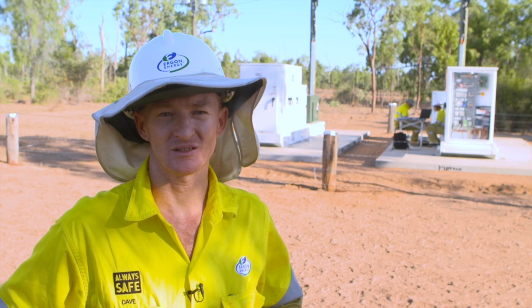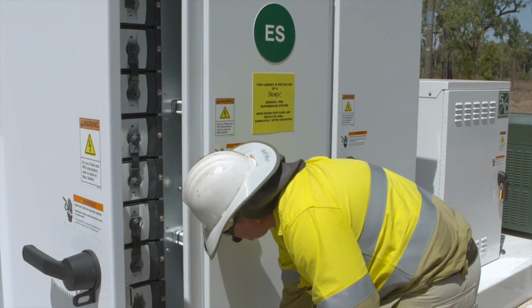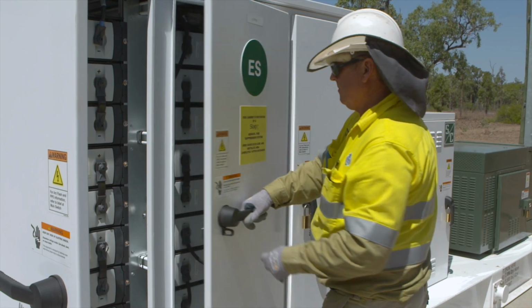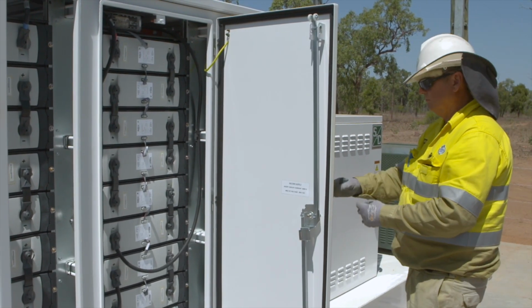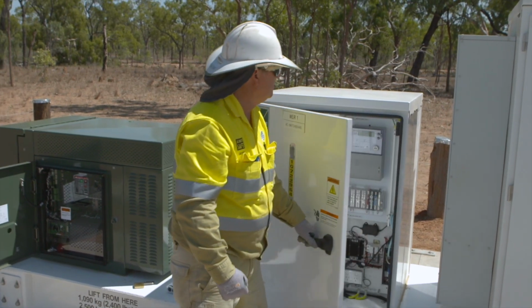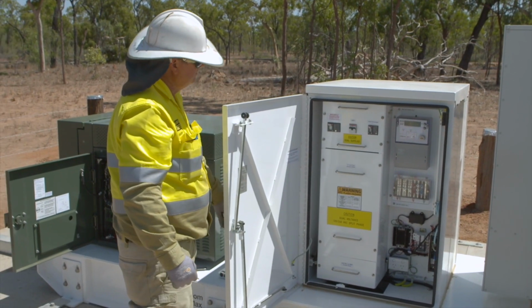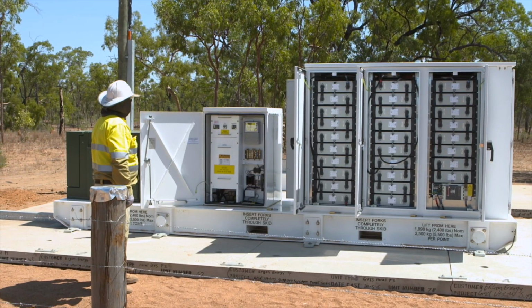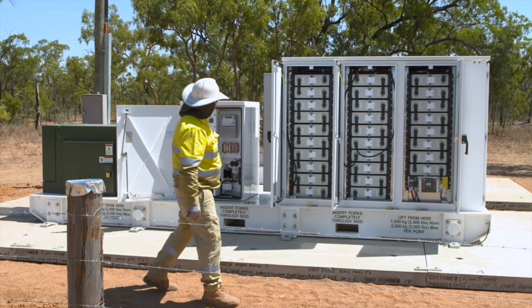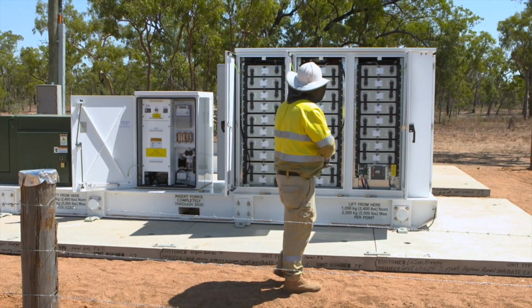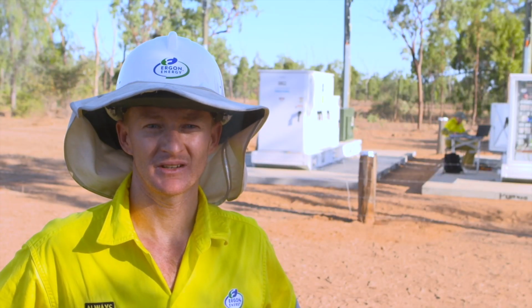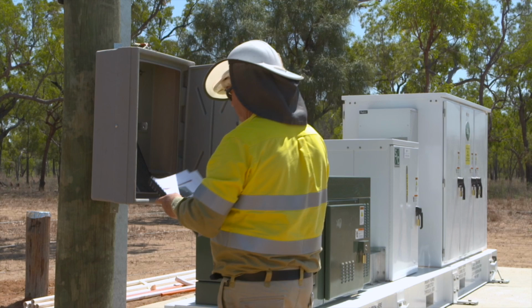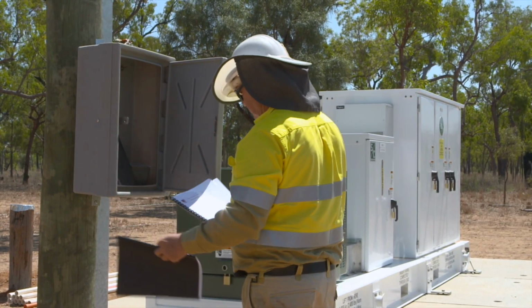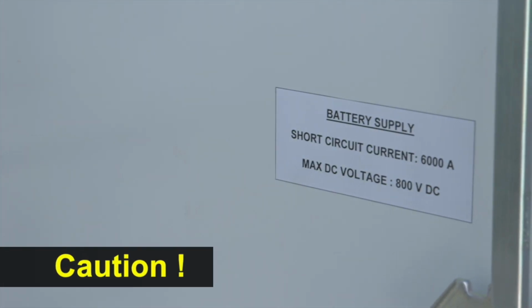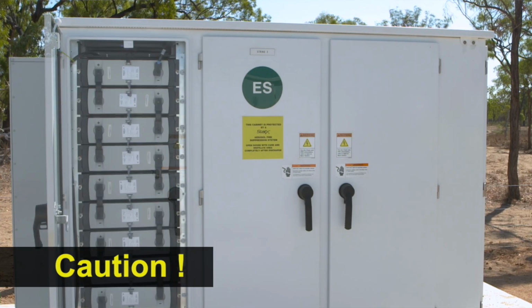A basic inspection shall be performed under the abnormal working situations such as fault or at the request of the GUSS engineer. It includes visual checks of the site and equipment such as door handles, status of circuit breakers, indication lights on electronics, or check inside the unit for anything unusual like vermin inside the control cubicle. More detailed information is in the manual, a copy of which is in the lockbox on site and on the process zone. GUSSs use lithium batteries and can generate up to approximately 800 volts DC. These batteries are always live.